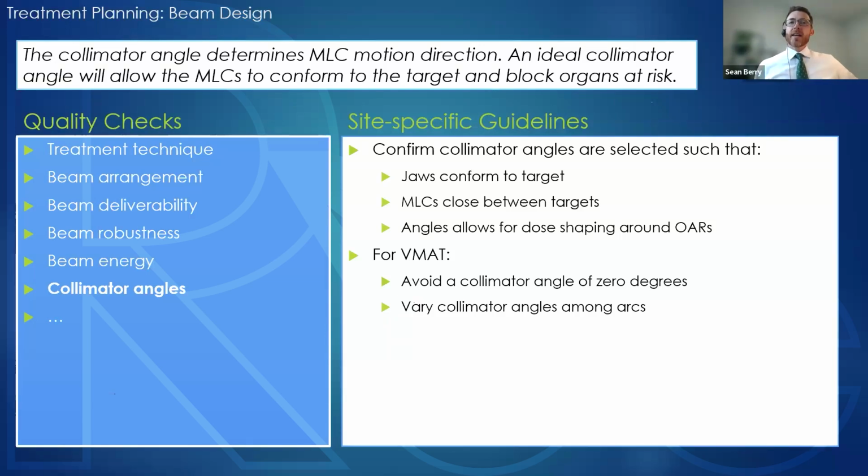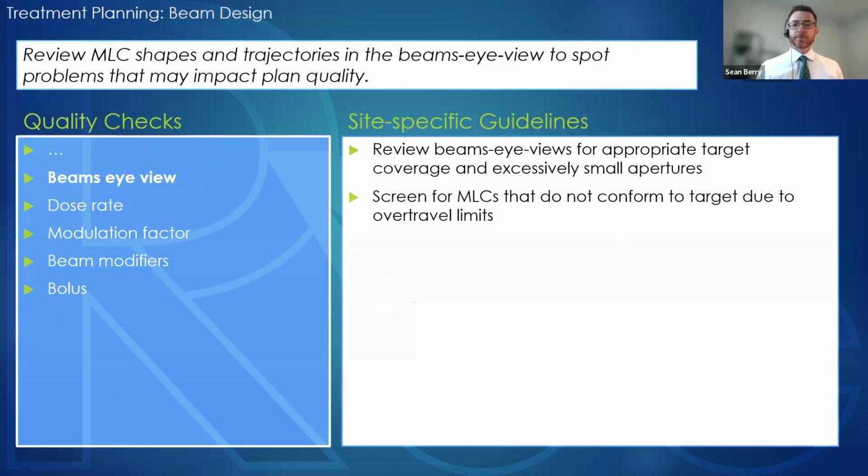So, again, stepping back as a plan checker, you always want to look at the characteristics of the dose distribution. We'll talk about the dose distribution in a minute. Where's the hot spot? Where are there streaks? Is there banding? And you want to ask, what is it about the beams that were chosen, or the collimator angles that were chosen, or the MLC that resulted in that? And can we reduce it by making some changes there?